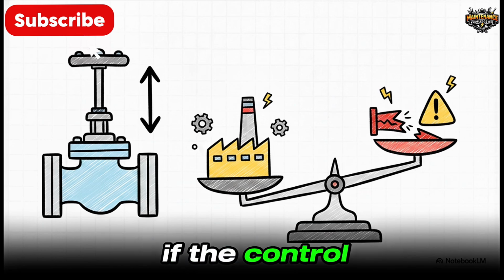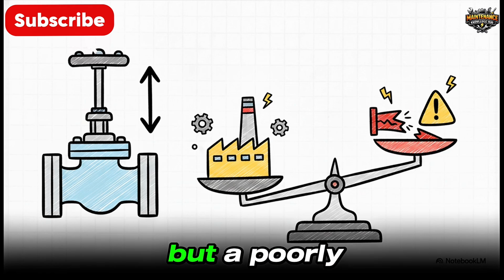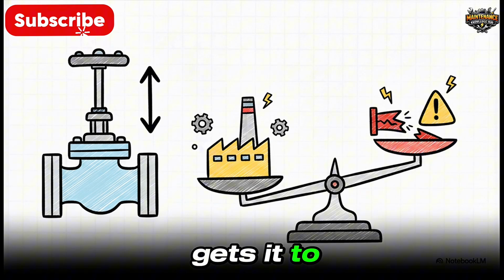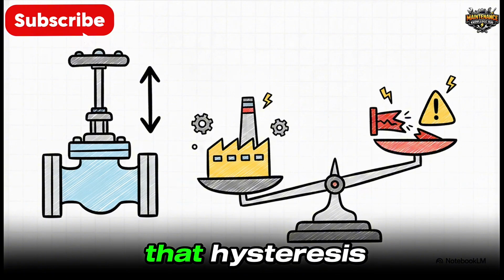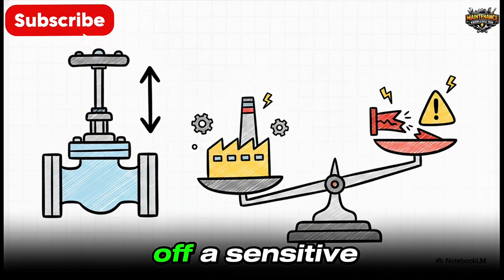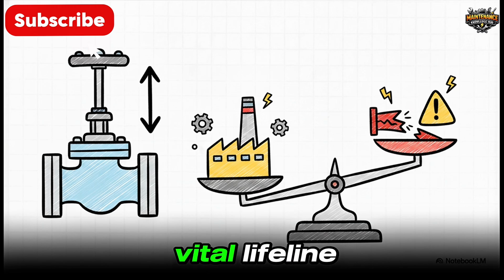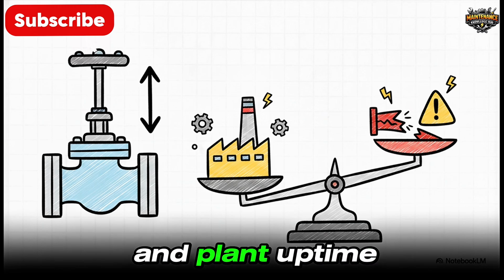Think about it. If the control system commands 45% open, but a poorly calibrated positioner only gets it to 42%, that tiny gap, that hysteresis, can completely throw off a sensitive chemical reaction. This isn't just a box to check. It is a vital lifeline protecting product quality and plant uptime.